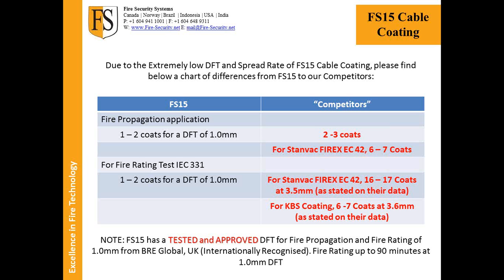So when we look at the fire propagation, or just the stop spread of flame, FS15 only needs 1 to 2 coats. The top side of a tray, as we saw before, is a 1 coat situation. It can take a heavier coat. There's no lagging or sagging of the coating or dripping, so you can spray a heavy coat straight over, but the underside you may put 2 coats on because you don't want anything to drip down. Everything is presentable. So it all comes down to how it's presented back to the client. The client gives us orange or black cable in tray, and we want to give them that, and it all looks lovely, and we want to give them white cable in a tray after coating, and it still looks lovely with 0 overspray.